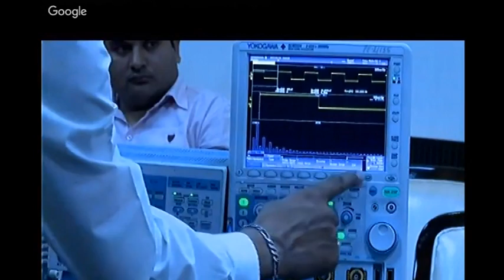Next is harmonics. You can see the harmonics in the instrument, and there is a numerical list of harmonics available too, up to the 40th order. You can plug in a pen drive and save it directly, and on a laptop or desktop it will open as an Excel sheet. This is harmonics. There is also I-squared-T energy measured in joules.